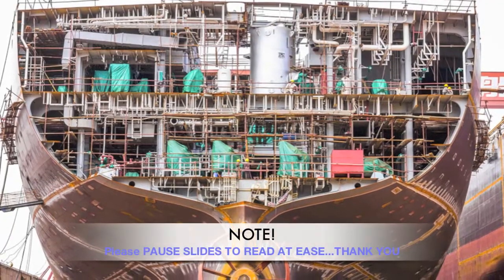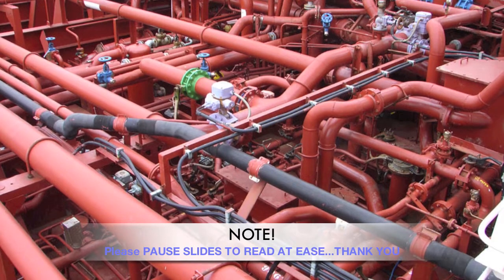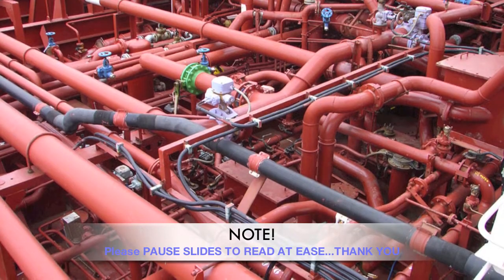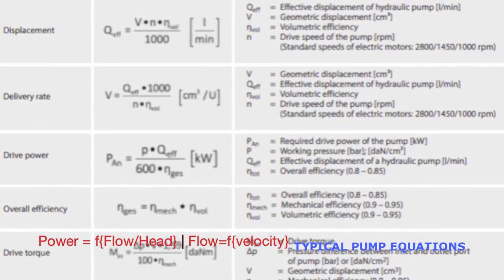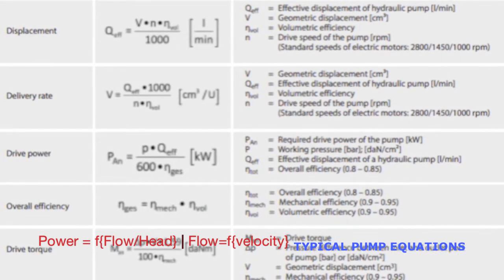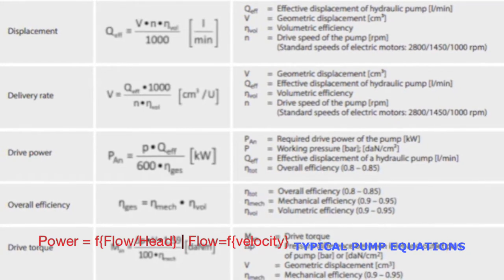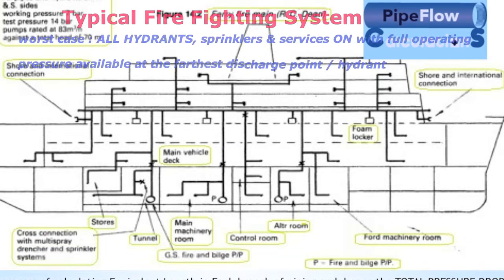So the overall agenda today is a hydraulic exercise to determine the pumping capacity and what will be typically the most optimum power that the pump is going to be operated at to do its desired function of pushing the water to its worst case duty of the firefighting system. And the worst case duty of firefighting system is pushing the water to the last of the hydrants further away from where the pump is.